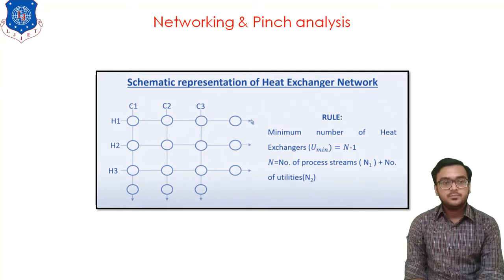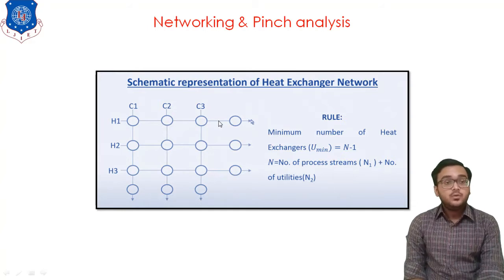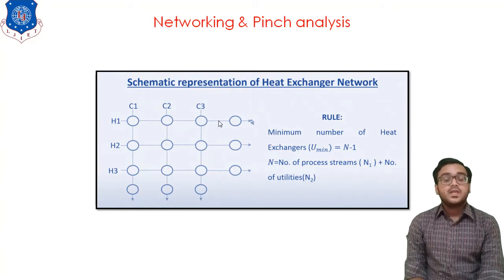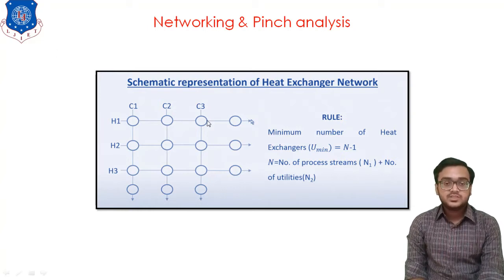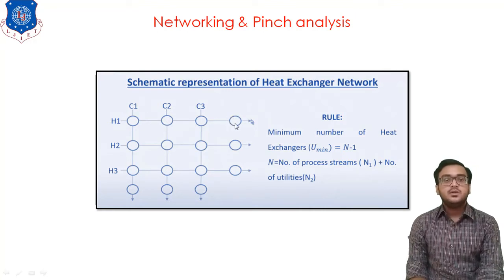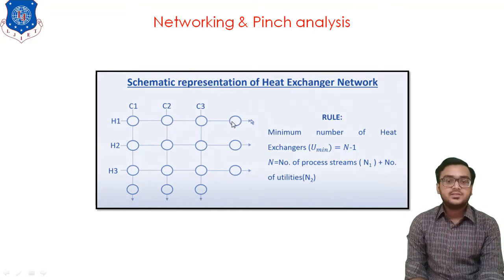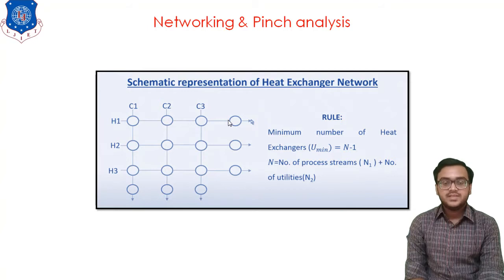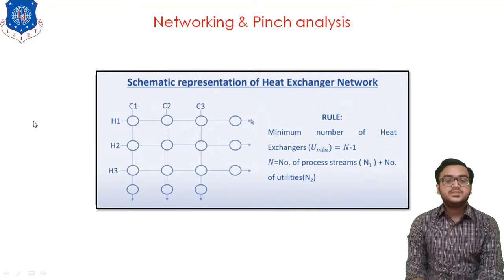Likewise, we have lots of streams H2 and H3. We require to arrange all streams in such a way that mutual heat exchange is possible between the streams, and we should require a minimum amount of external utility — hot utility or cold utility. The thumb rule is: the minimum number of heat exchangers required equals N-1, where N equals the number of streams plus the number of utilities.